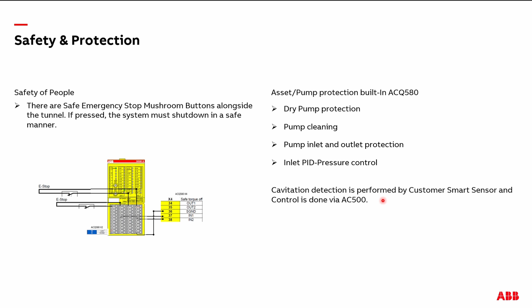And the cavitation detection, as I mentioned earlier, is performed by the customer's smart sensor. Although the ACQ 580 has a built-in feature, it's not so possible to measure the cavitation here, because there's one point which you must take care of. The frequency converter can only measure this if there's not so much damping between the pump itself and the motor. So the vibration during cavitation must be detected by the motor or the motor torque in order for the converter to notice this. But it doesn't matter. In this case, we have the smart sensor, and we can detect it via the smart sensor.